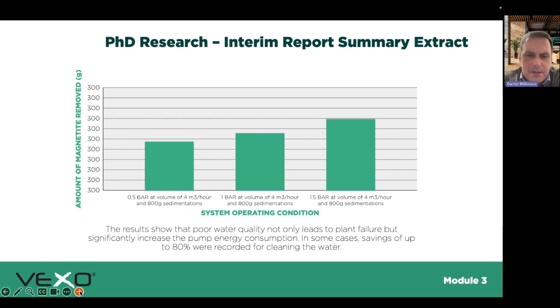What we also found was the relevance of pressure and the amount of sediment added to the system. The higher the pressure, what we actually found was we were pulling more out of the unit, but it was blocking much quicker, which one would expect. Because in this case we were using the system pump and only had the one pump, that's the correlation. But typically most systems are operating over a bar in a commercial system.